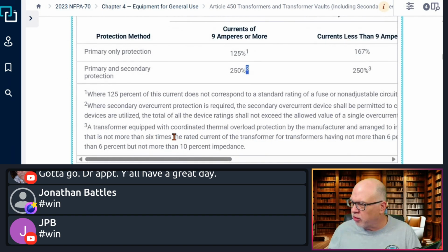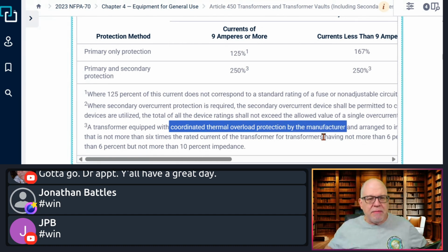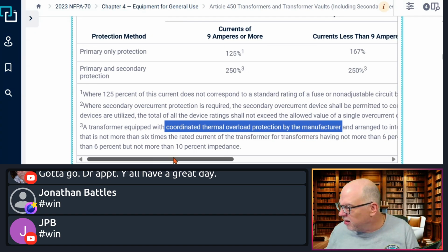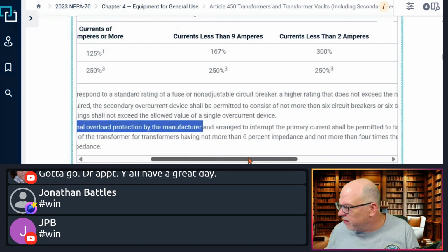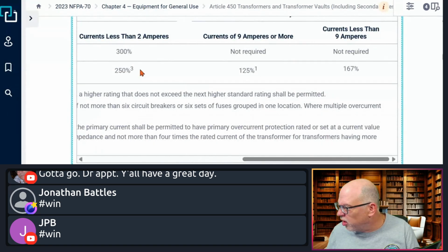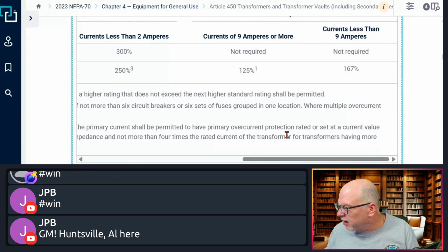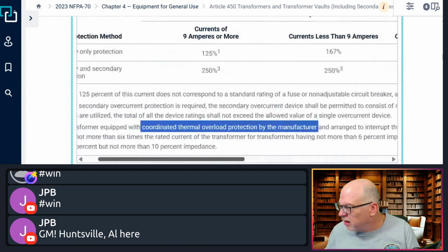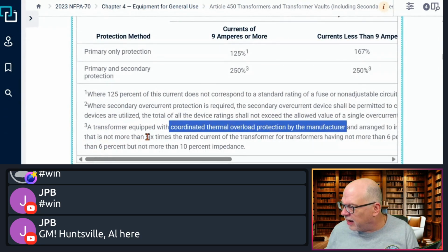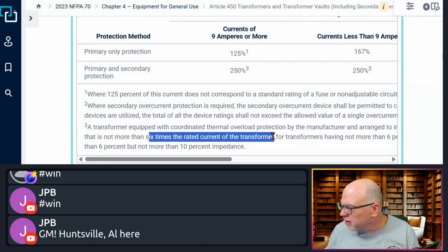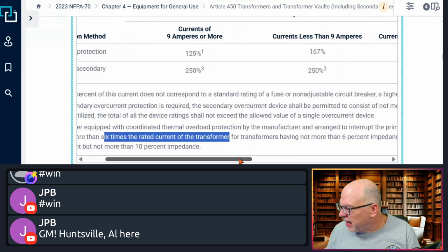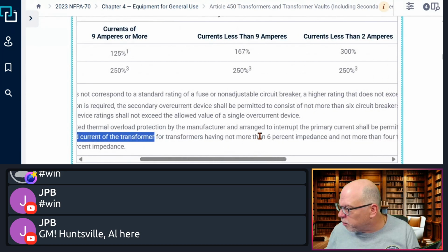That is dealing with transformers that are equipped with what's called a coordinated thermal overload protection by the manufacturer. That is already built into the transformer, and if that's the case, then again, that gives you some allowances to exceed. Okay, so what does that say here? It says in this scenario, because of this little note, the primary overcurrent protection is rated or set at a current value that is not more than 6 times the rated current of the transformer, for a transformer having not more than 6% impedance.